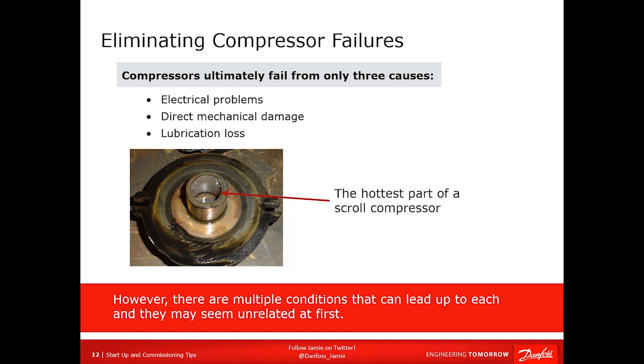A lot of times people are measuring the inside or internal overload, which happens to be open. They condemn the compressor and away you go. However, if you don't eliminate the reason why that compressor overheated or why it ended up with a short in the windings, it's going to happen again. If you get lucky, you might catch it. But the whole idea of the startup and commissioning is to make sure you catch any electrical problems. Make sure you don't have floodback or slugging, right? And make sure that you don't overheat the compressor, lose your lubrication, or your oil goes out somewhere and never comes back, right? All these things can easily be caught and rectified during a startup and commissioning process. They don't need to take a ton of time, but they need to be done.